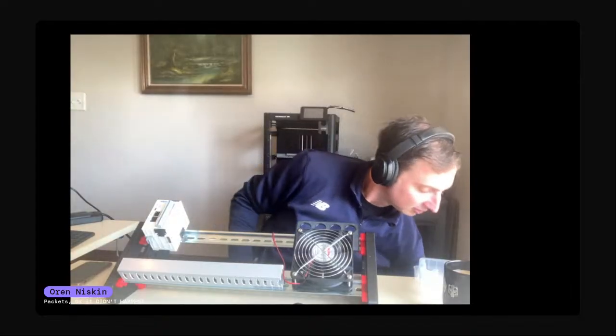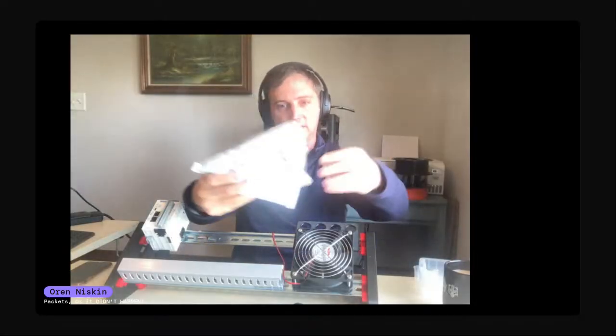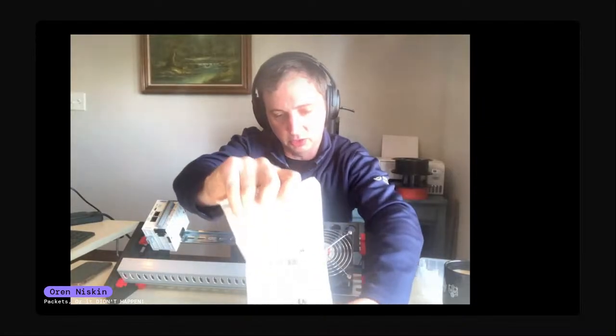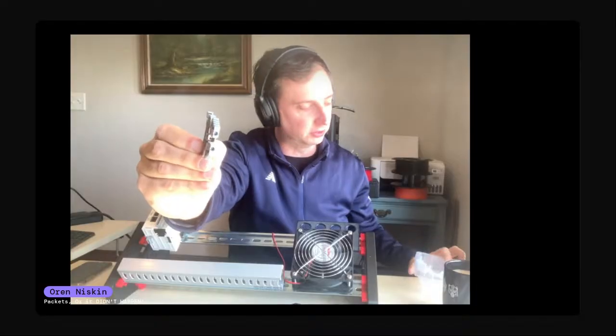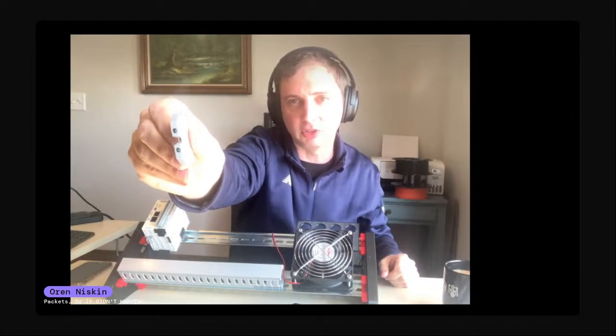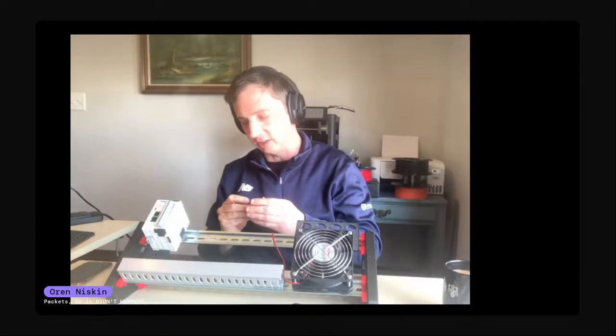The next part of our kit is terminal blocks. This is a terminal block, a place where you put one wire in the top and one wire coming out the bottom, and this is where you make connections in the field. If you have a cabinet, you wire everything up, and at the bottom there will be a bunch of these where the wiring goes out to the field, to the motors, valves, temperature sensors, hydraulic systems, and all that kind of stuff. It all comes through terminal blocks. Terminal blocks are kind of like the workhorse of the electrical panel.